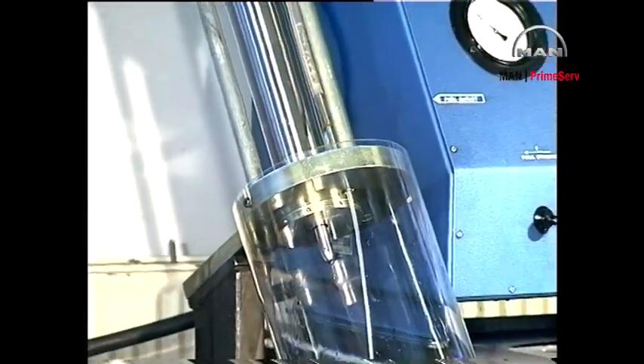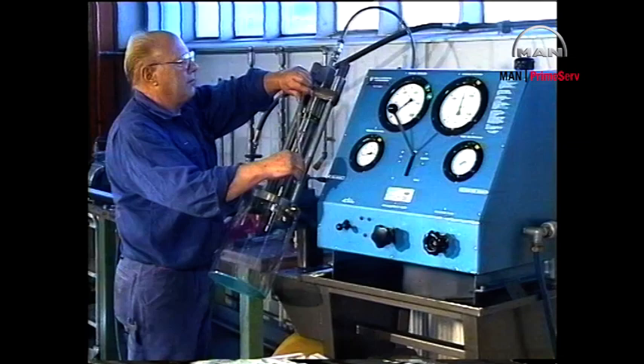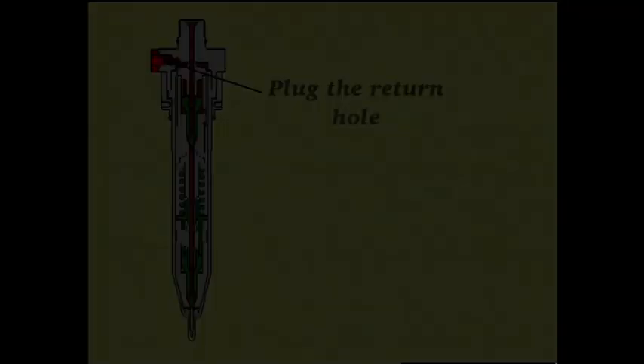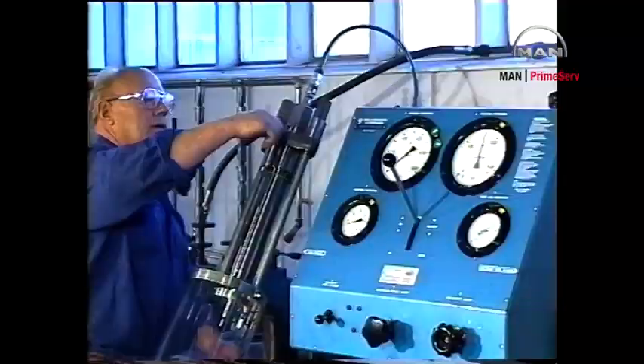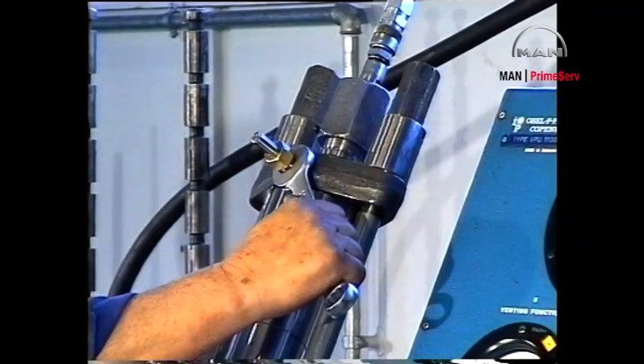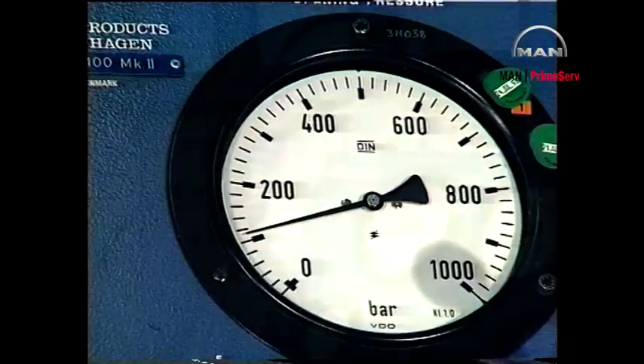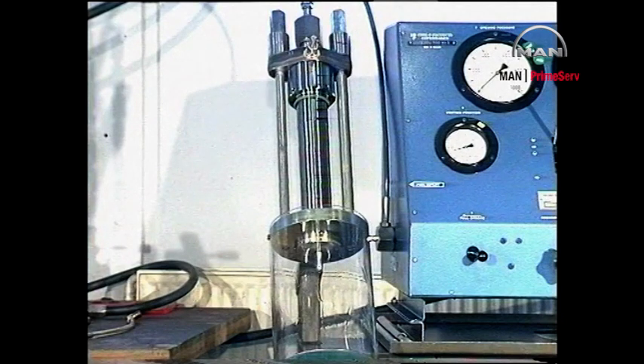Slowly fill the valve by pumping at low pressure until fuel oil, without air bubbles, flows from the fuel oil return pipe. Remove the fuel oil return pipe and block the outlet hole with a gasket and a plug screw. Increase the pressure to about 100 bar and move the control handle to the closed position. The pressure should now remain at 100 bar. If oil leaks at the union nut, replace the O-ring seal of the valve head. If oil leaks at the lower end of the valve, replace the O-ring seal on the spindle guide.